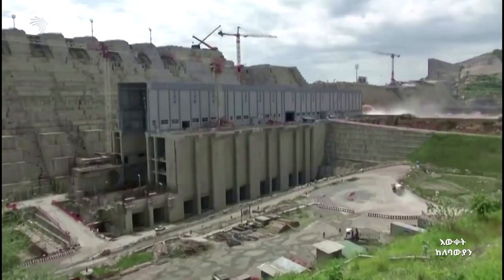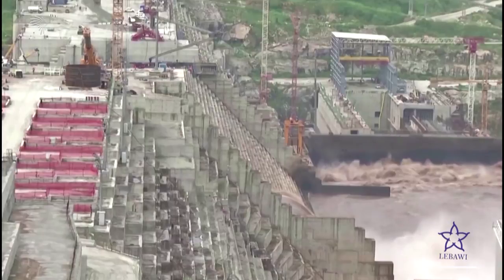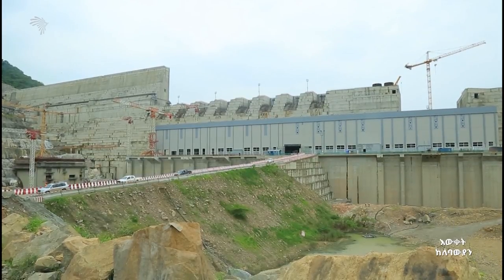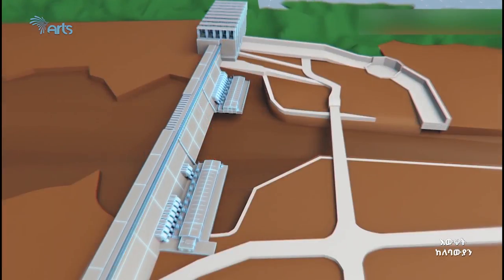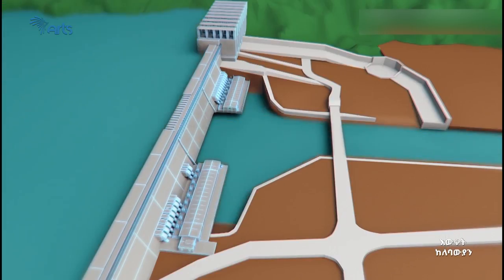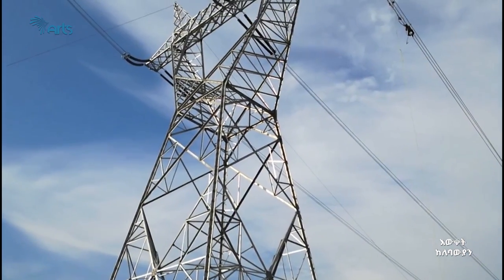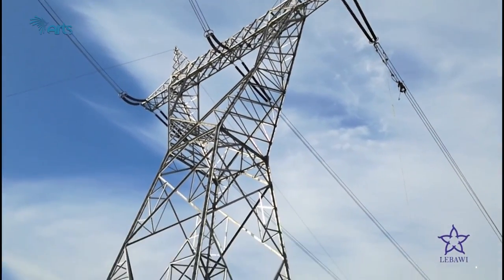Now let's integrate this physics with the Grand Ethiopian Renaissance Dam, or GERD. The GERD is located 50 km east of the border between Sudan and Ethiopia. It was initially designed as a roller-compacted concrete dam, 155 m high, with 74 km³ storage capacity and 6000 MW installed turbine capacity. The main dam body has two powerhouses: the right powerhouse has 10 Francis turbines with 3750 MW total installed capacity, while the left powerhouse has six Francis turbines with 2250 MW installed capacity. Each turbine has a flow capacity of 270 m³/s. A 500 kV switchgear will also be constructed to transmit power from the power station to the grid.